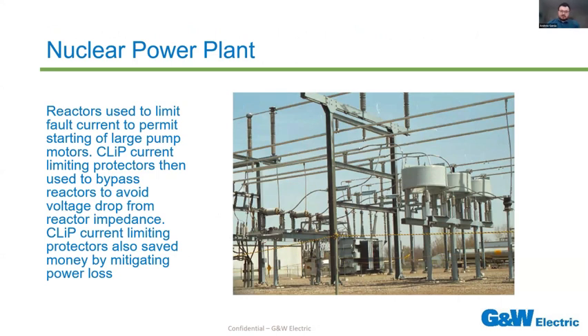So here's an example of a nuclear power plant where a current limiting solution was used. Here, reactors were used to limit fault current to permit the starting of large pump motors. Their equipment that was in charge of starting these large pump motors was underrated. However, when they used these reactors, they found out they incurred a pretty significant power quality issue, which could affect the long-term reliability and efficiency of these pumps. So as a result, they ended up using the CLiPs, which is a lower impedance device than the reactor, to bypass around that reactor in order to avoid that voltage drop. So not only did that avoid that voltage drop, but it also mitigated a lot of that power efficiency loss from the added impedance and saved that nuclear power plant a significant sum of money as well.